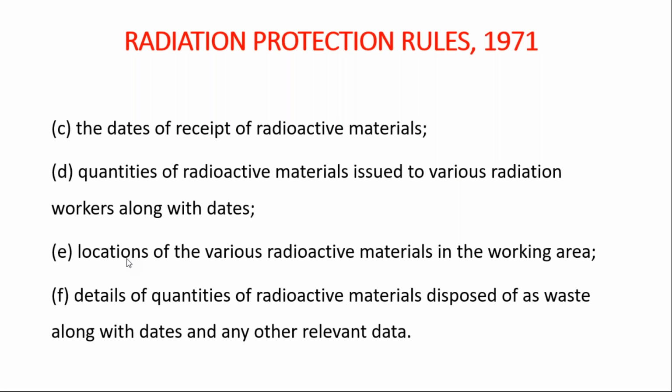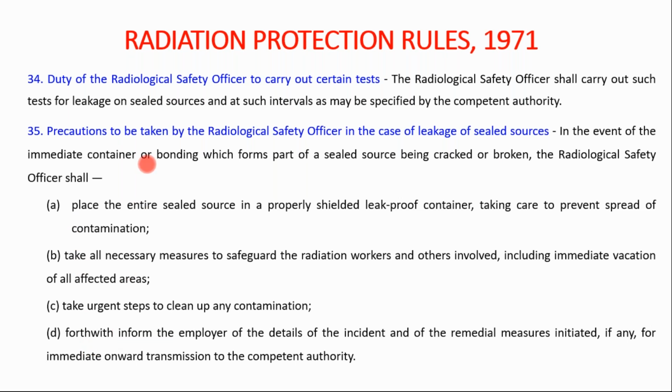So with reference to this rule, if the radiological safety officer conducted a leakage test and found some leakages beyond the permissible limits as far as the act and these rules are concerned, then the radiological safety officer's duty is to seal that source. In the event of the immediate container or bonding which forms a part of a sealed source being cracked or broken, the radiological safety officer shall do the following activities.